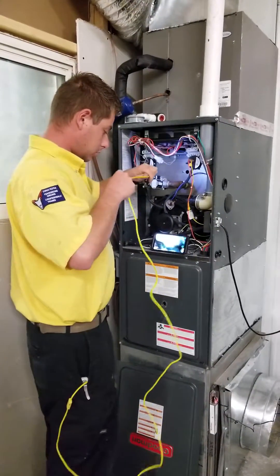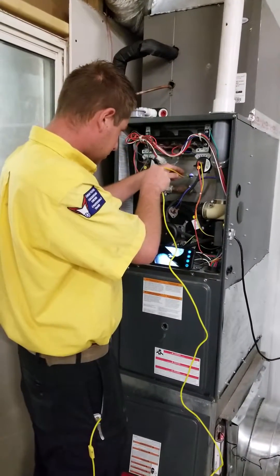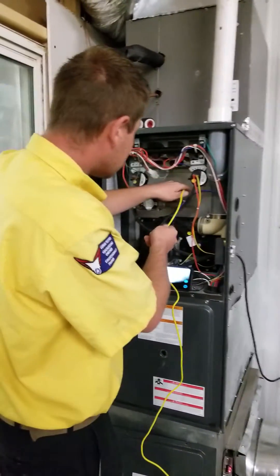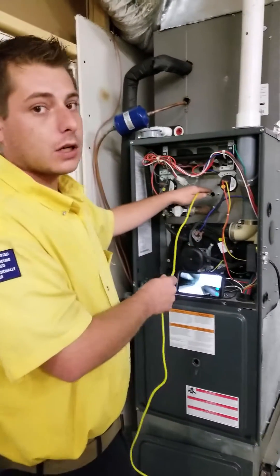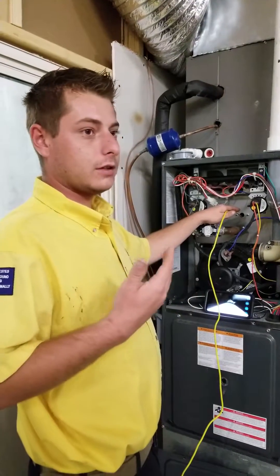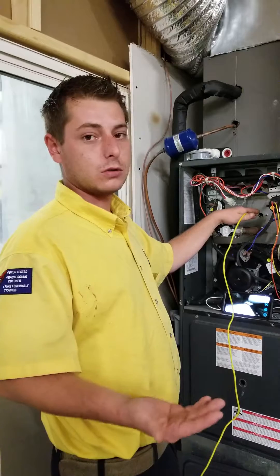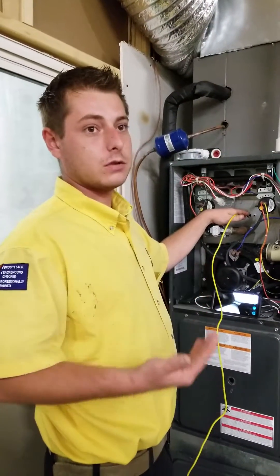We're going to go in here and check the heat exchanger, make sure there's no cracks or stress points. Why do you need to check for any cracks in a heat exchanger? Because if you have cracks, it gives off carbon monoxide into the house, which could ultimately kill you if you get too much of it. So we don't want anything bad to happen to our customers, so we check the heat exchanger when we come do our fall PMs to make sure that their system is safe to run.